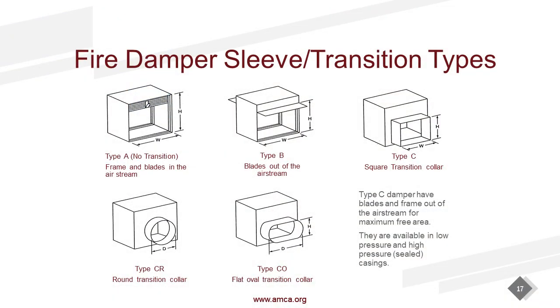The last three here are your type C's transitions, right? We have square to round, square to oval, square to square. These would be considered your 100% or your maximum free area dampers, lowest pressure drop. But again, that damper has to grow in size. Your opening has to grow in size to accommodate those transitions.